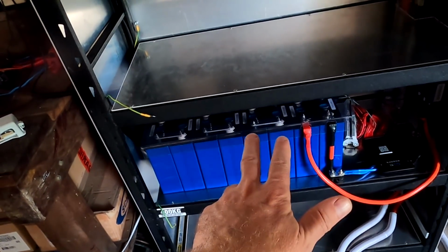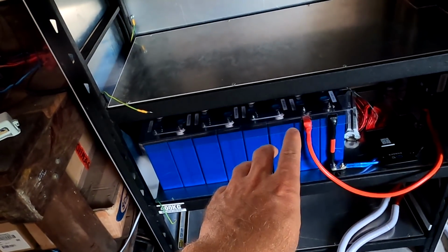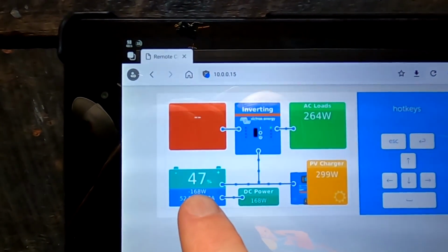We are doing the full load test on our battery here. This is the new battery bank I installed 4 days ago, during the flood, so I've had this online for a week now, I can't believe it. It's so good because it has doubled my battery storage capacity. Now if I'm at work, I don't need to worry that my battery gets full with nobody turning on any load at home, and I'm wasting all this beautiful solar energy. Because now if it says 47%, this is almost like 100% with the old battery. But now we've got so much capacity it basically never gets full, which is not good either.